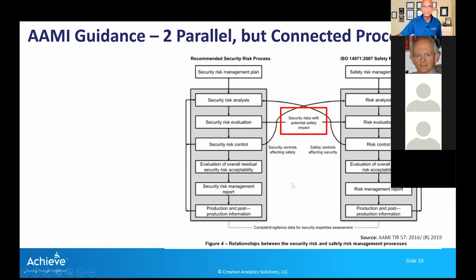So here is the table. Here is a chart that they show in the TIR 57, and some of you may already be familiar with it, but I wanted to show this to everybody in the group. In that guidance, they recommended a parallel path approach. Security risk management plan decoupled from safety risk management plan, but there's a link. Wherever you have security risk with potential safety impact, they need to be evaluated within the framework of ISO 14971. And whatever risk controls you implement, go back to security analysis, see if there's an impact, and vice versa. If there's a security risk control, see if there's an impact from the safety point of view.